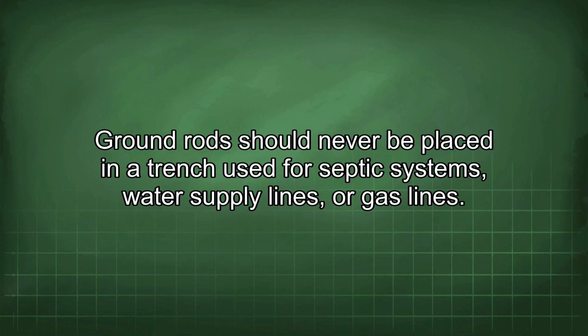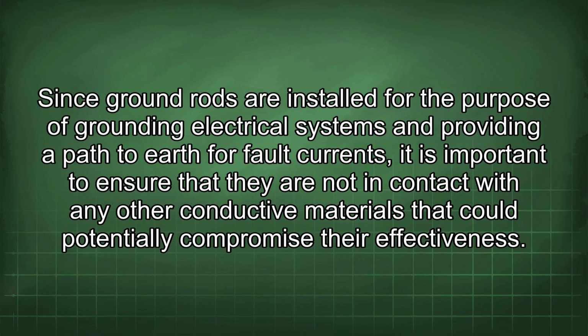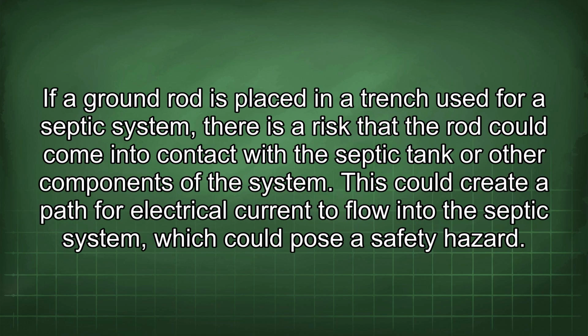Ground rods should never be placed in a trench used for septic systems, water supply lines, or gas lines. Since ground rods are installed for the purpose of grounding electrical systems and providing a path to earth for fault currents, it is important to ensure that they are not in contact with any other conductive materials that could potentially compromise their effectiveness. If a ground rod is placed in a trench used for a septic system, there is a risk that the rod could come into contact with the septic tank or other components of the system.